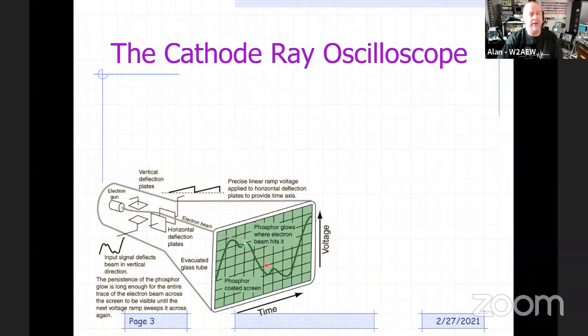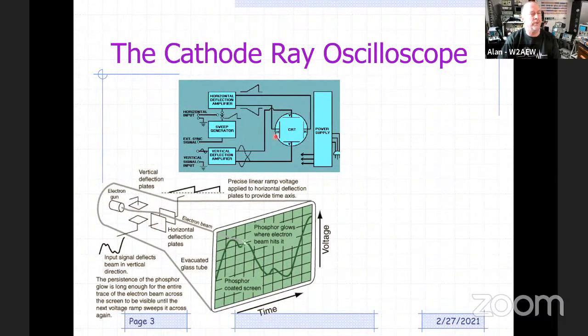And essentially, it's kind of like a TV tube in the sense that you've got an electron gun firing an electron beam at the phosphor on the screen that glows as the beam is swept through. That beam is directed to go across and up and down based on horizontal and vertical deflection plates. And those plates are driven by amplifiers that get input signals, to drive the beam back and forth through the horizontal circuit, and then also to drive them vertically through your input and then the vertical amplifiers in there. So this is really a very basic block diagram of an analog scope.